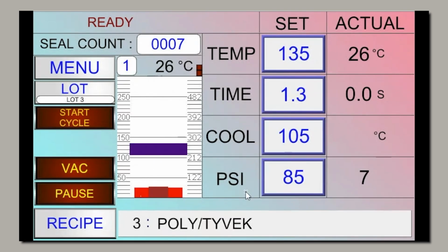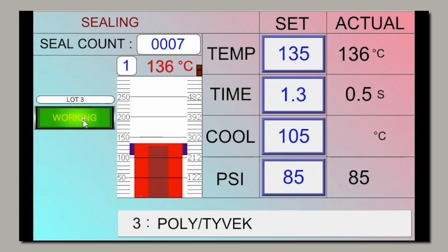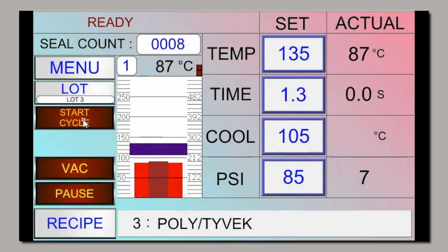The right-hand side of the user interface shows the process parameter information. The left column is the set values and the right column shows the live or actual values. We can demonstrate the live values by pressing the foot pedal or Start Cycle button. Temp will flash red until the actual value is below 60 degrees Celsius.